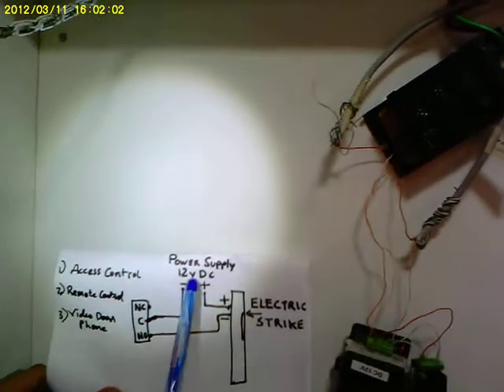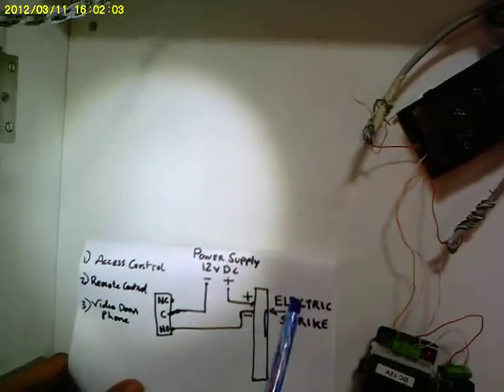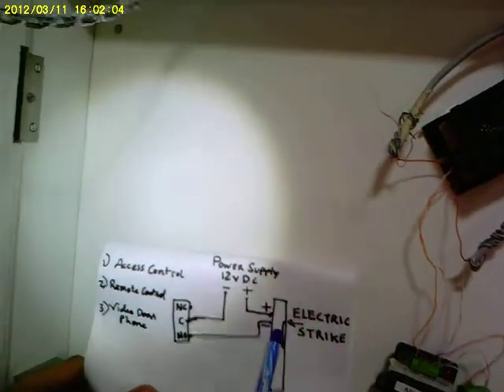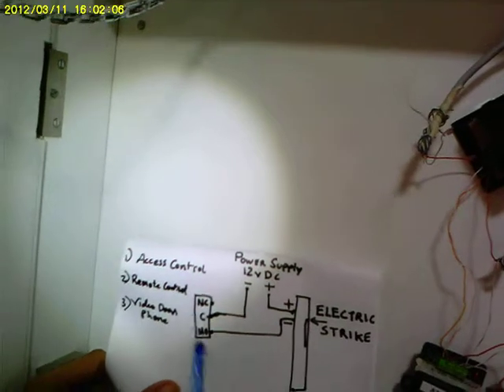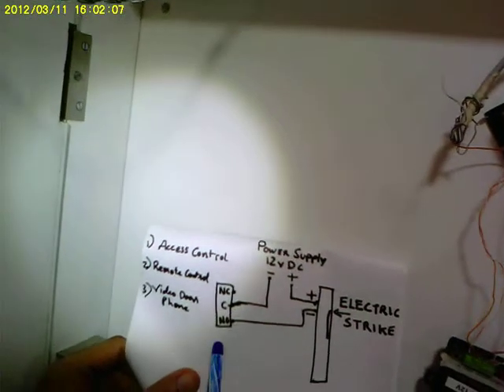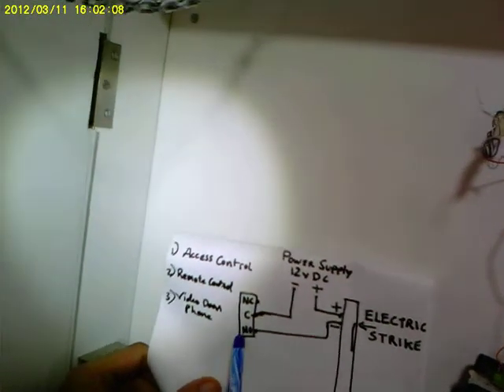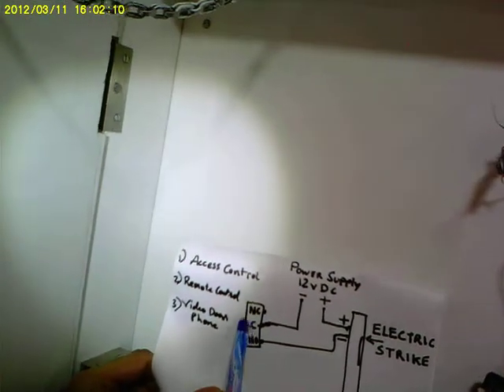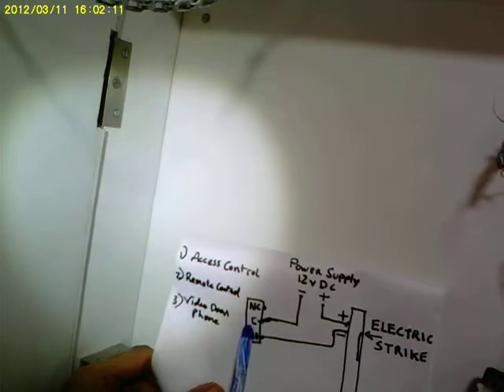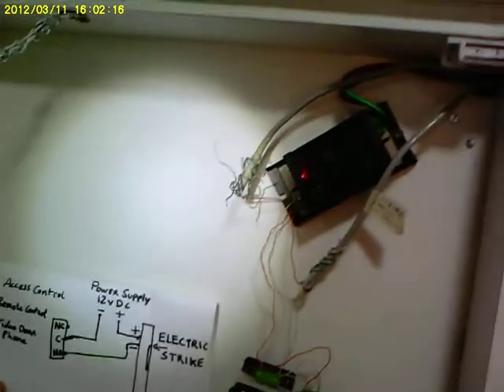So, if you see here, the plus is connected to the plus electric strike. The minus is routed via the controlling relay. Now, the NO of the relay and the common from the relay goes to the minus of the power supply.